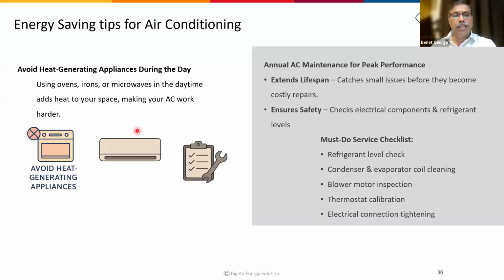Then see whether heat generating appliances are operating in the air conditioned space. Unnecessary operation of heat generating equipment will increase the energy consumption. Then it is better to do at least annual maintenance for peak performance, because the refrigerant can leak, and low refrigerant pressure will increase the energy consumption. The condenser, especially the outdoor unit, can accumulate dust, which reduces the heat transfer. Hence the efficiency of the air conditioner will come down. It is also important to check the blower motor and the thermostat calibration, whether the thermostat is actually measuring the room temperature or is malfunctioning.